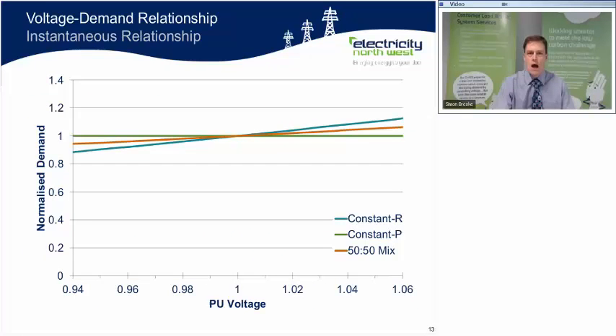So, I want to discuss a little on the voltage demand relationship. The graph you see here describes the relationship of voltage and demand for different types of loads. If we start with the blue trace, which represents a constant resistance load, we'll see that as the voltage increases, so does the load. And as the voltage decreases, the load will decrease. And that's a squared relationship. If we look at the green trace, that's a constant power load. And on this, the load is invariant as the voltage changes.